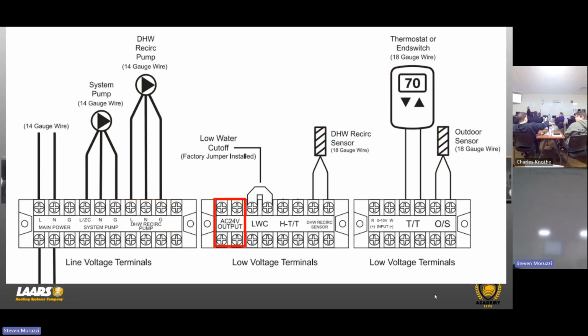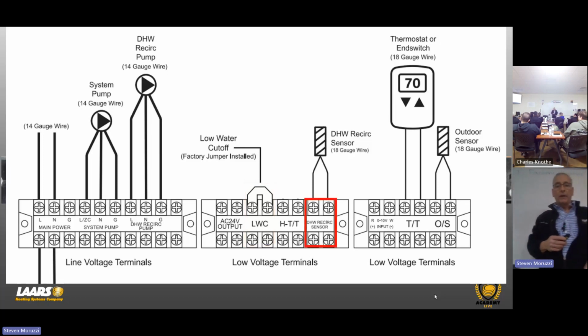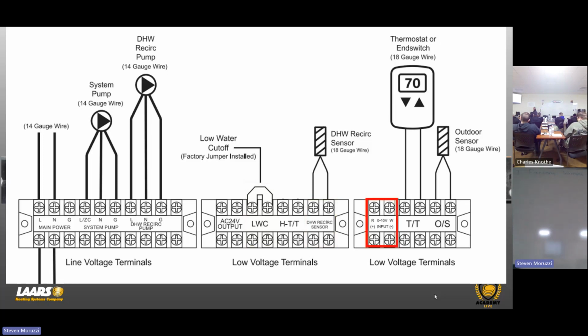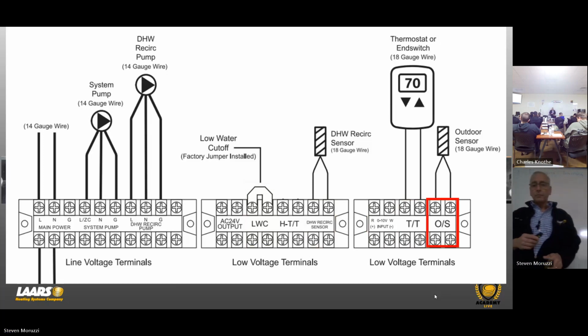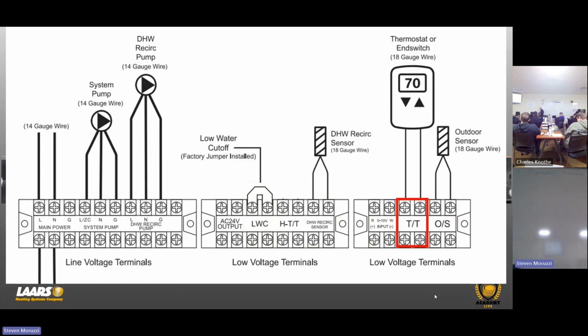You've got your 24 volts we talked about. That is strictly for the additional low water cutoff that you have to add out in the field. And then your low water cutoff terminals, you would remove that jumper. We have something called HTT, which I'm going to come back to. Domestic recirc, if you're going to use your sensor, you're going to wire that up on that low voltage terminal. 0 to 10 inputs. Again, Tekmar, we're seeing about 25% of those here in New York with air controlling modulation. TT, right? That's your thermostat demand, or end switch. And then lastly is your outdoor sensor.